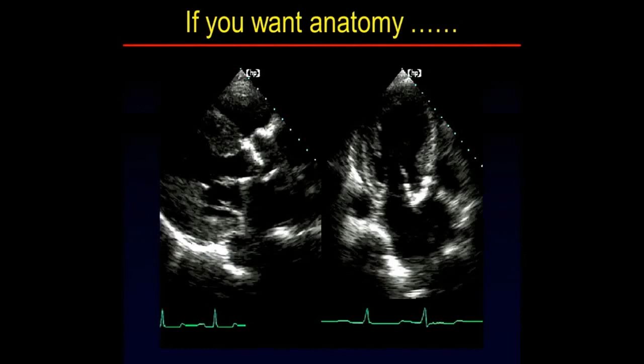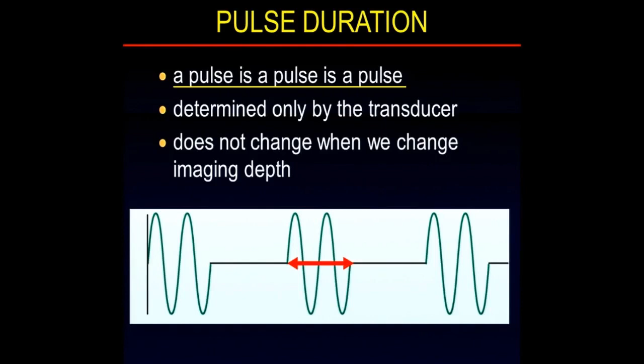So pulsed ultrasound has 5 additional descriptors. Guess what? There they are. And we'll see this again. So the parameters are, first, pulse duration. The actual time that the pulse is on. It has units of time and it's super short, like 3 microseconds. So transducers do this. Beep, beep, beep. The pulse is very, very, very short. That's the pulse duration. Now what I say is a pulse is a pulse is a pulse. The pulse never ever changes if you have a transducer in your hand. What changes is the time between the pulses when you change depth of view. If you're imaging shallow, you don't have to wait very long to send out the next pulse. So shallow imaging sounds like this. If you image deep, you have to wait longer for the reflections to come back. Deep imaging sounds like that. But the only thing we're adjusting is the listening time. The talking time remains constant.